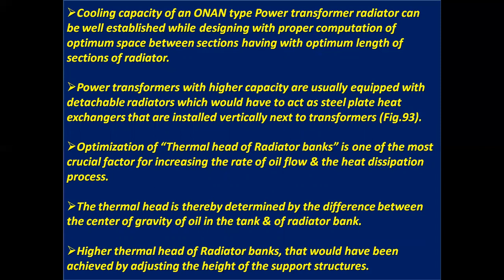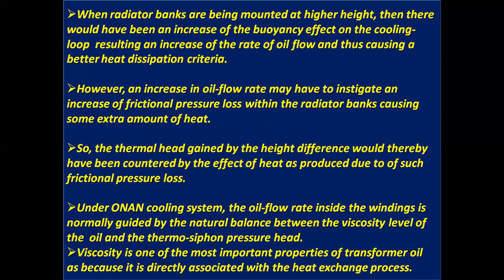Optimization of the thermal head of radiator banks is one of the most crucial factors for increasing the rate of oil flow and the heat dissipation process. The thermal head is determined by the difference between the center of gravity of the oil in the tank and that of the radiator bank. A higher thermal head of radiator banks can be achieved by adjusting the height of the support structures of the radiator banks. When radiator banks are mounted at a higher height, there is an increase of the buoyancy effect on the cooling loop, resulting in an increase of the rate of oil flow and thus better heat dissipation.